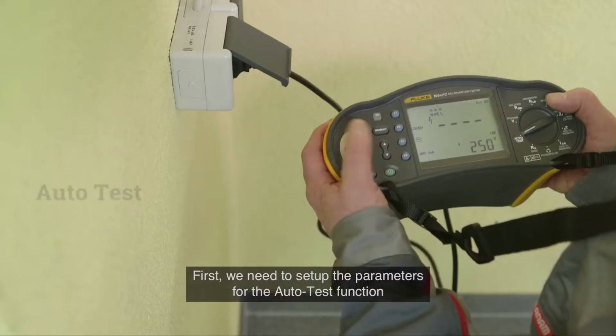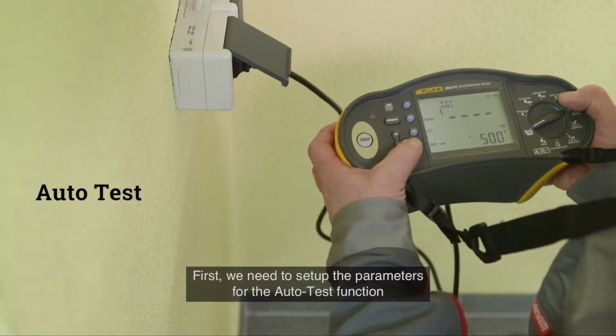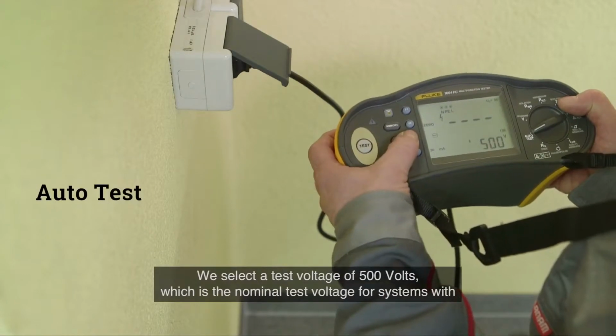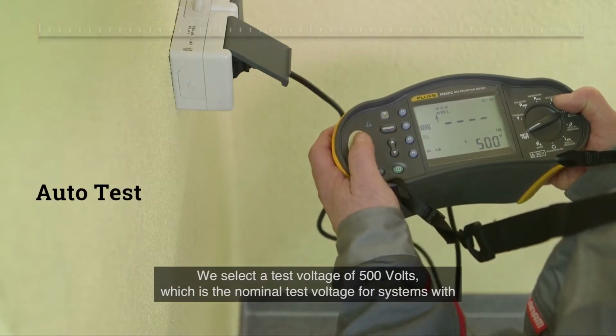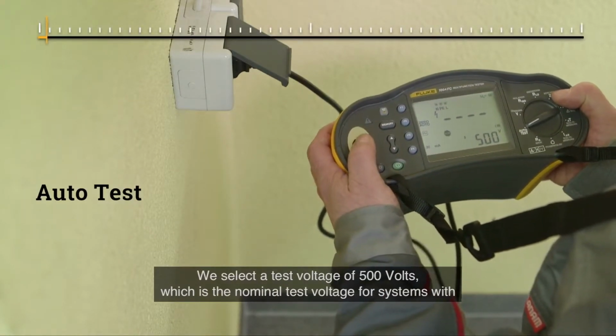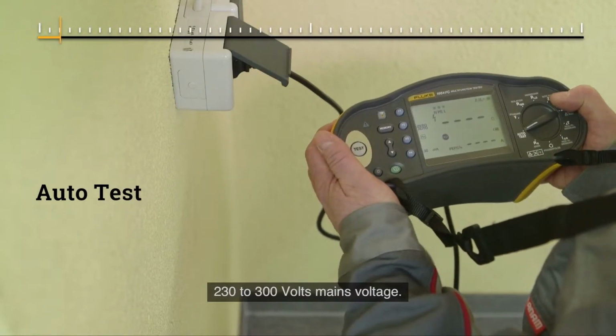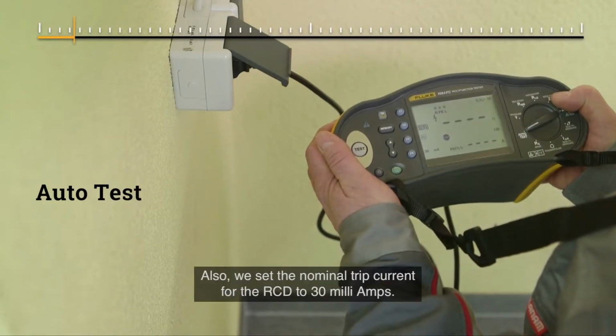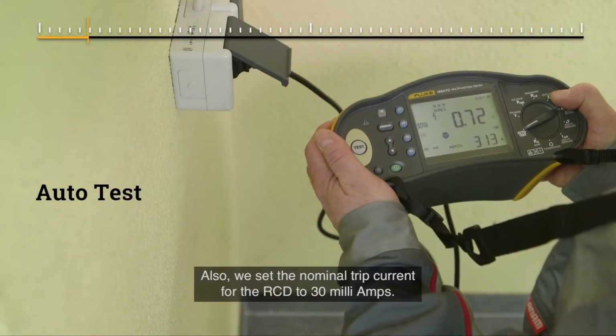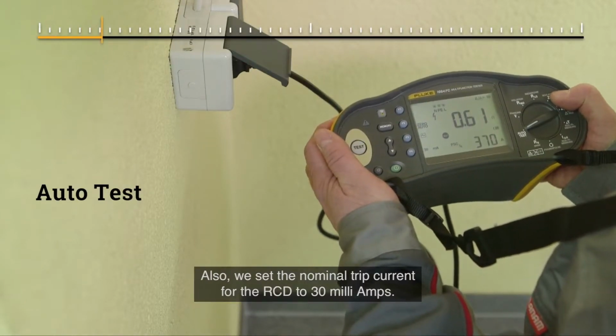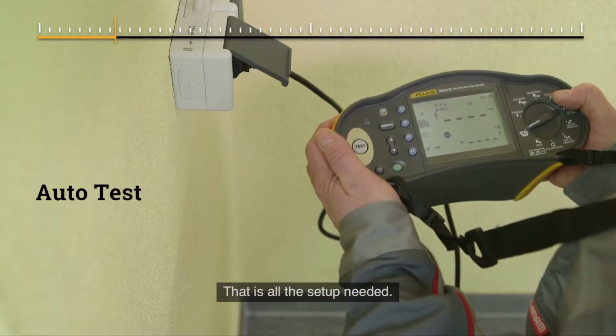First, we need to set up the parameters for the AutoTest function. We select a test voltage of 500 volts, which is the nominal test voltage for systems with 230 to 300 volts mains voltage. Also, we set the nominal trip current for the RCD to 30 milliamps. That is all the setup needed.